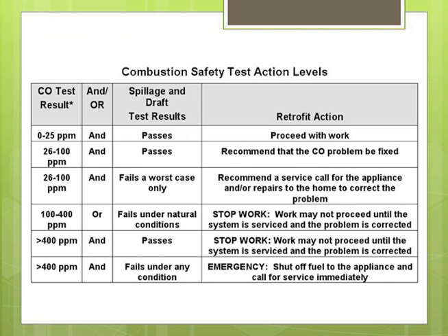These are the action levels. If you measure carbon monoxide between 0 and 25 parts per million and your flues are working properly, you proceed with the work. You have to take more and more stringent measures depending on how concentrated the carbon monoxide is. If you turn on almost any gas oven and take a carbon monoxide reading right away, it will be in the 600 range — really dangerous. But as it warms up and works for a few minutes, it will go down to hopefully below 25, somewhere around there, if everything's working properly.